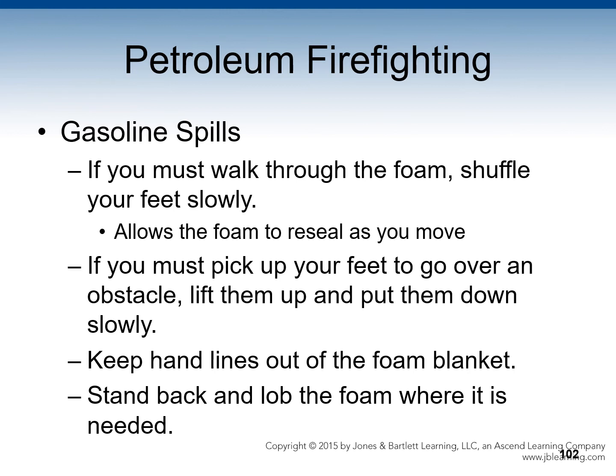If you must walk through the foam, shuffle your feet slowly to allow the foam to reseal as you move. Do not pick up your feet as you walk. If you must pick up your feet to go over an obstacle, lift them up and put them down slowly. Also try to keep hand lines down out of the foam blanket. The best course is to stand back and lob the foam to where it needs to go. This helps prevent breaking the foam blanket.